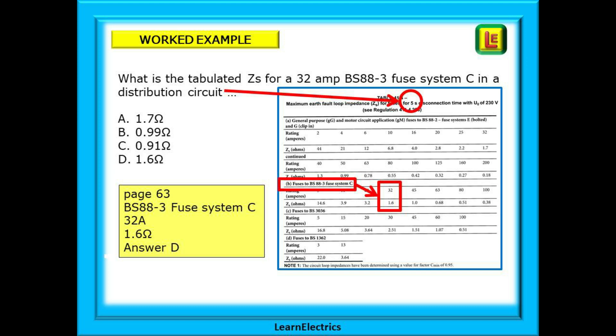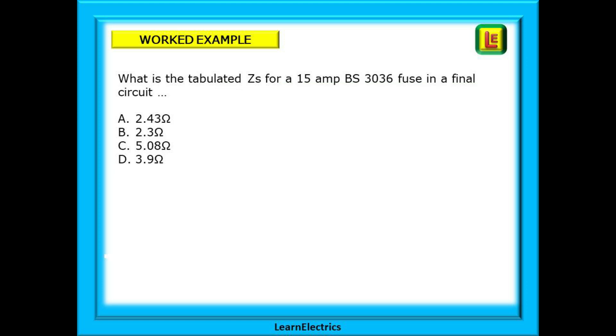The question tells us it is a distribution system which means a five second disconnection time. Find BS88-3 system C fuses but be careful there are two different types of BS88 fuses on this chart. Only one is correct for this question. Find 32 amps and the answer is 1.6 ohms answer D.